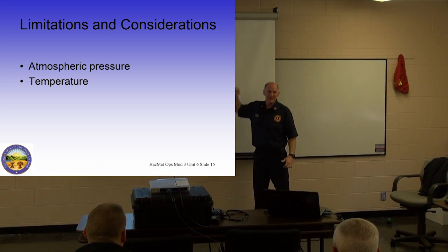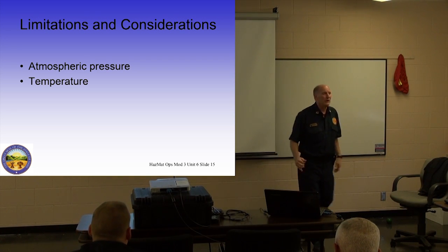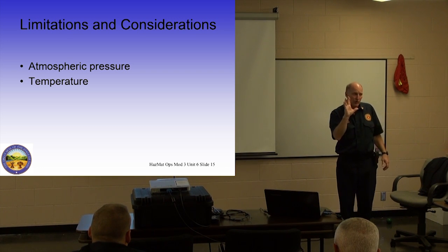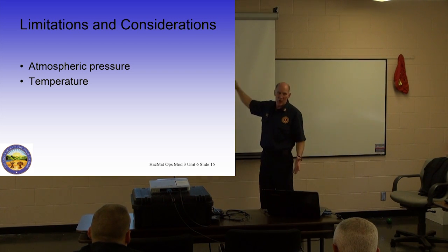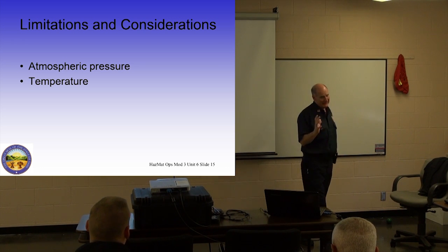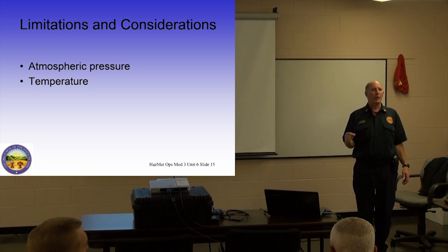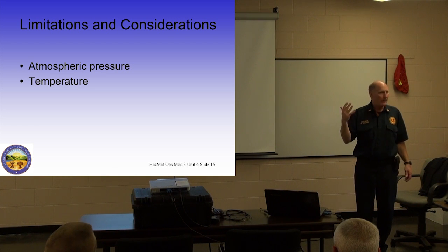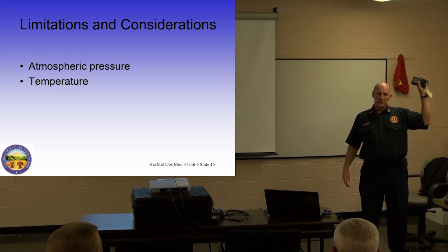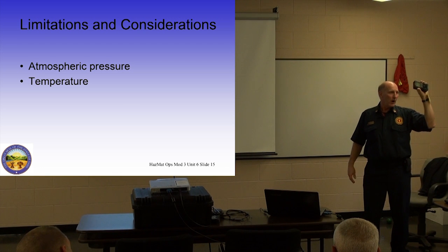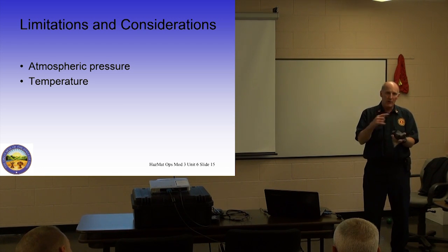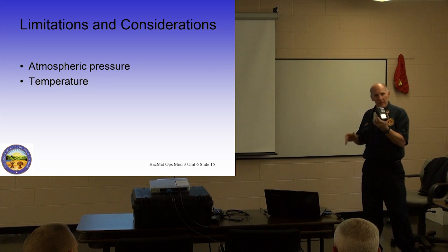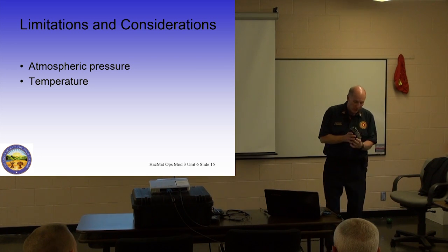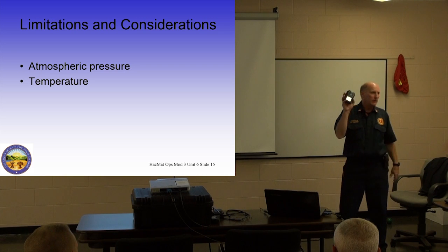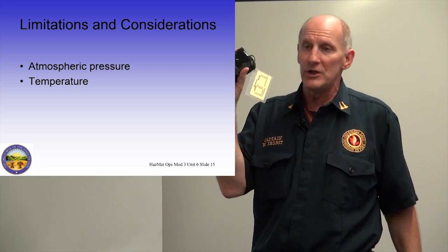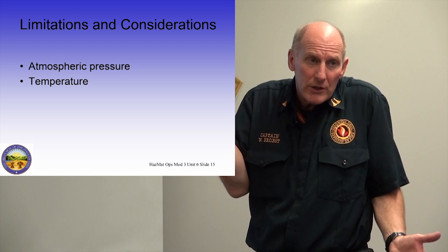There is temperature limitations. Atmosphere, elevation, humidity, these are all of the things that can change the O2 level and make it inaccurate. I want you to be aware of those things. I know it's tough. You're going to have to start this on a cold winter day in the truck, and then you're going to have to look down and hopefully you're not getting monoxide readings off the truck. And then when you jump out of the truck and you head to the front door, the O2 may change a little bit and you may be totally confused. All I'm telling you is that's the instrument. There's nothing we can do about it.